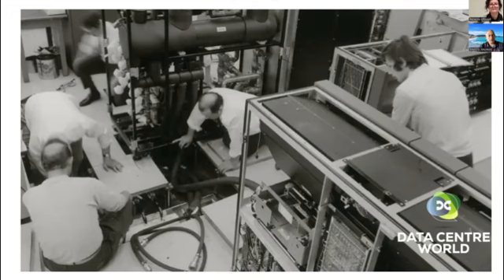After that, people started to use air-cooled computers, and they forgot where the raised floor came from, and they started to use this raised floor to deliver cold air. Because if you ask anyone from where it is better to deliver the cold air, they will say from the top down, because cold air is heavier than hot air. And when you ask why in that case we push the air from the bottom up, no one has an answer. So this is the answer.